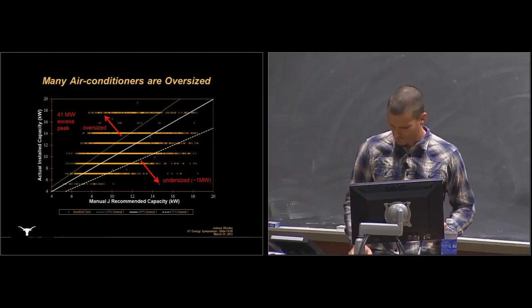Ducts are notoriously leaky, which is not a surprise to anyone in this industry. Austin Energy recommends that anything above 10% leakage get sealed, because your duct system typically runs through the attic, so leaks just send cold air into the attic, and that's not doing you any good because you're paying for it. Other studies show we're on the low end, but still similar. All of these systems over 10% leakage lead on average to about 18% excess energy consumption, because that much is going straight into the attic.